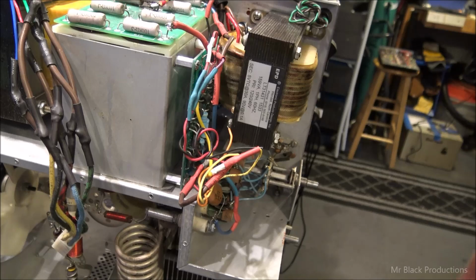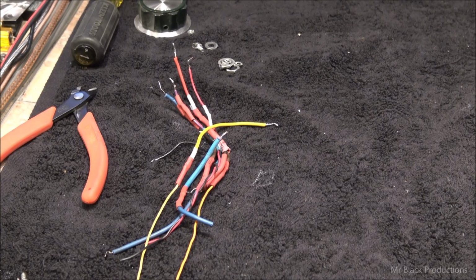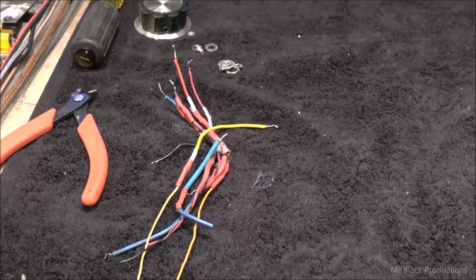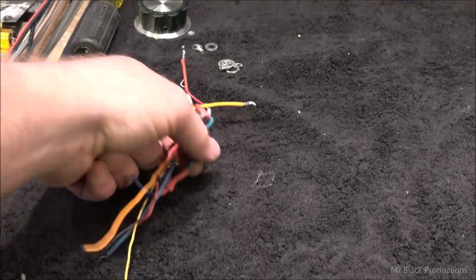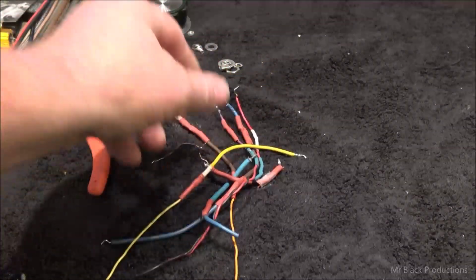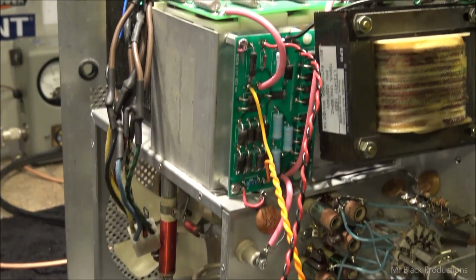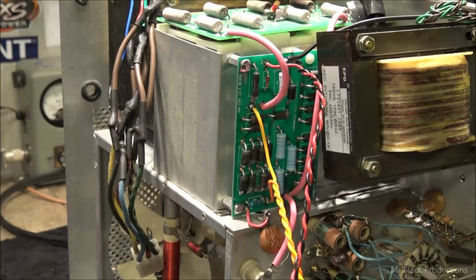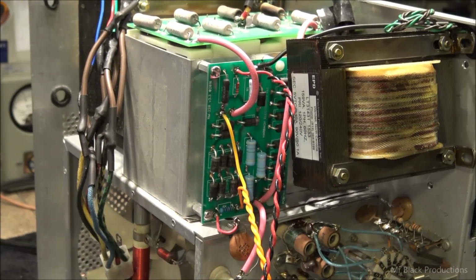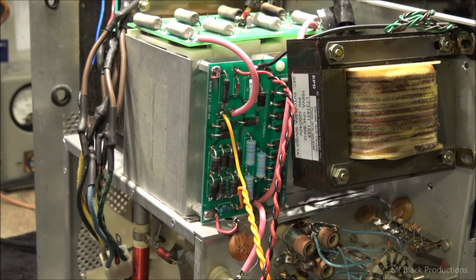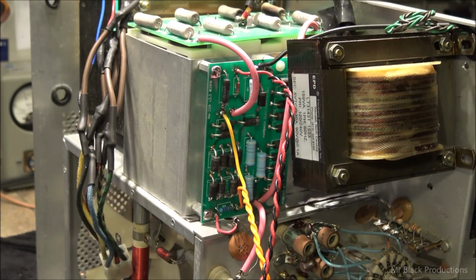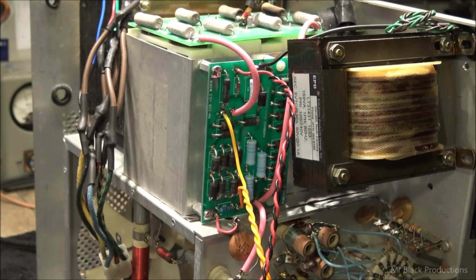Now to take it all apart and rewire the high voltage board. And I'm glad I've wired a couple of these over the years. So we just removed all of this hibby-jibby here. And we've completely rewired the high voltage board, which thoroughly tests. I can't believe it. With all this burned up schmoo up top, up here on the rectifier, on the capacitor bank.